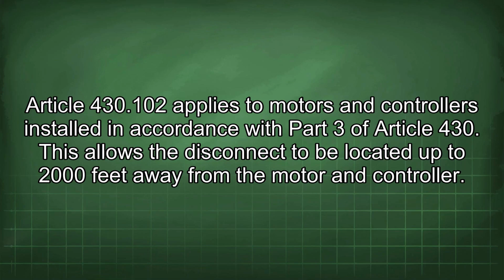Article 430.102 applies to motors and controllers installed in accordance with Part 3 of Article 430. This allows the disconnect to be located up to 2,000 feet away from the motor and controller.